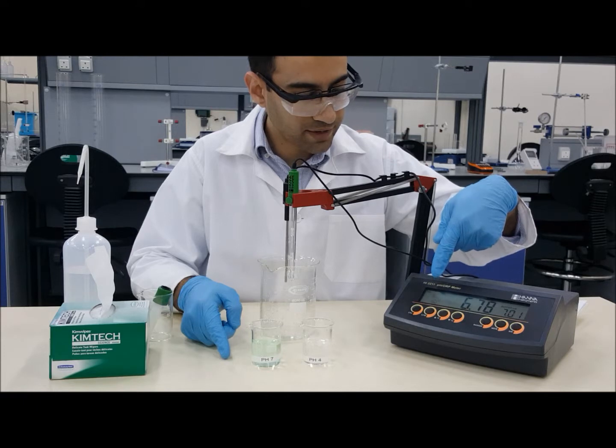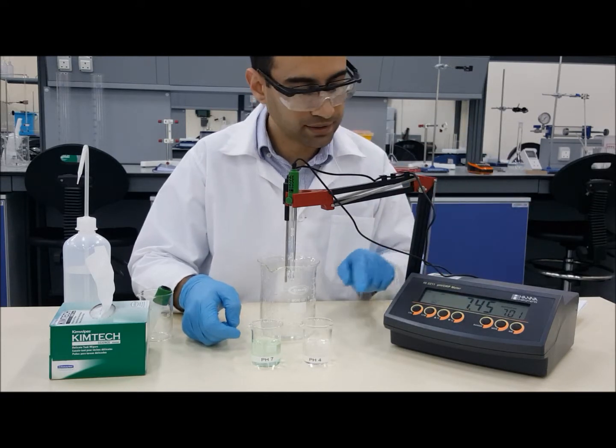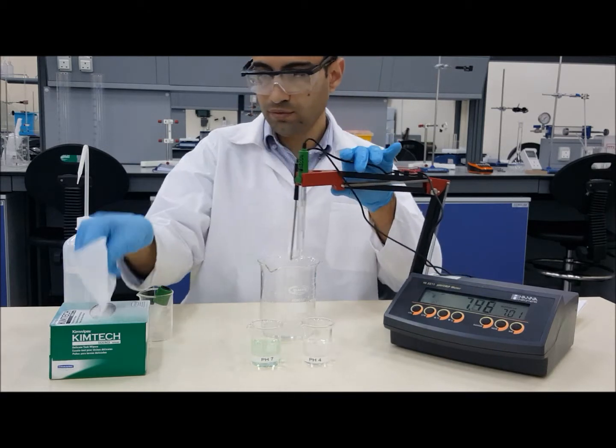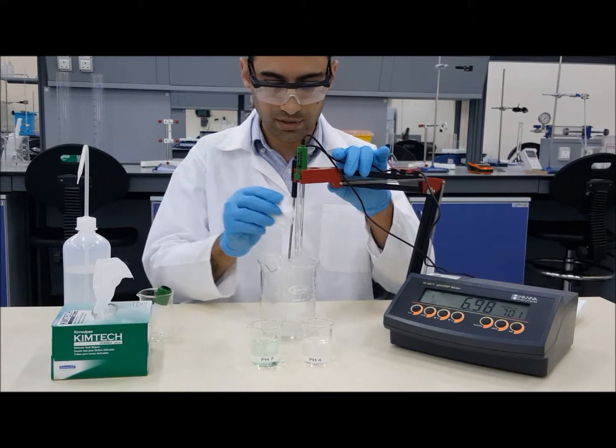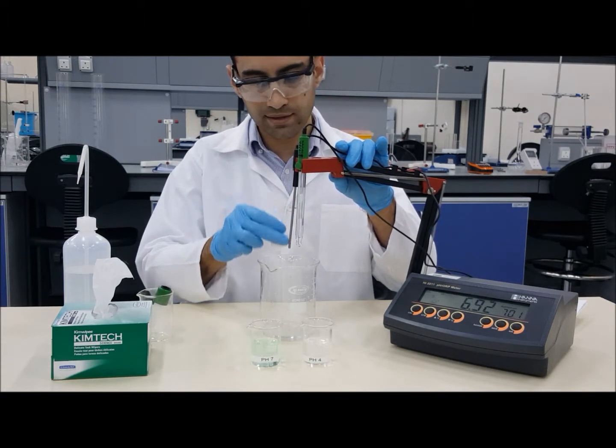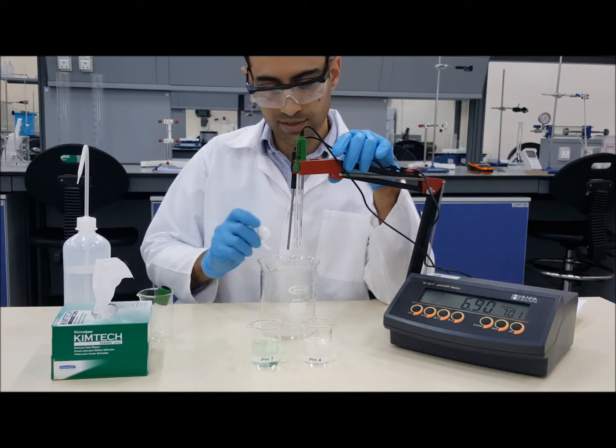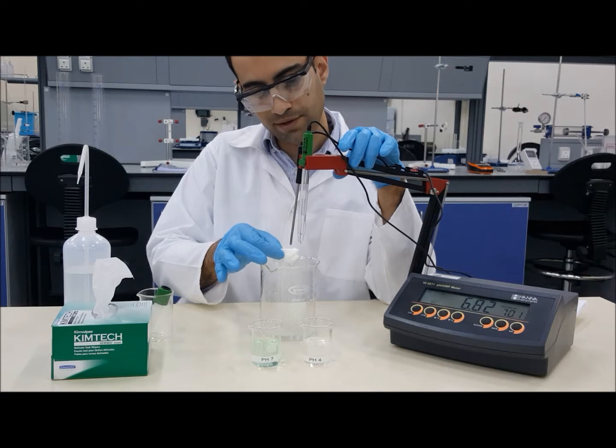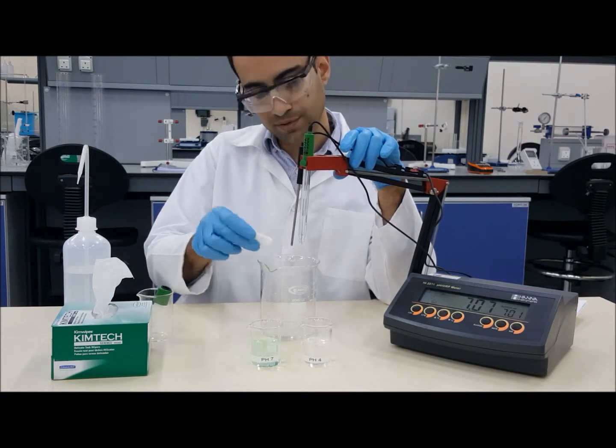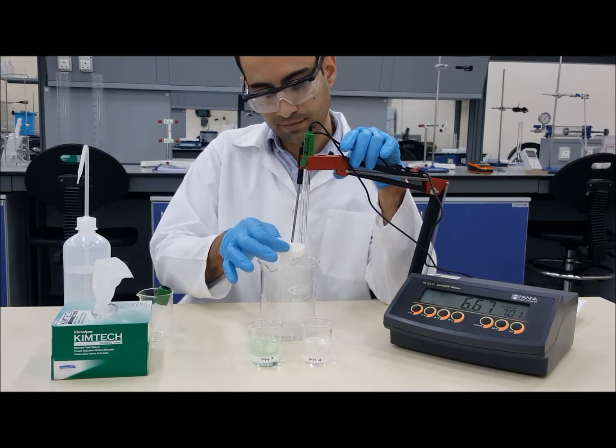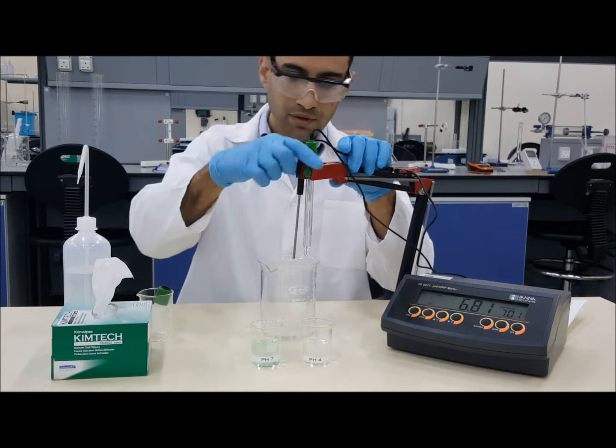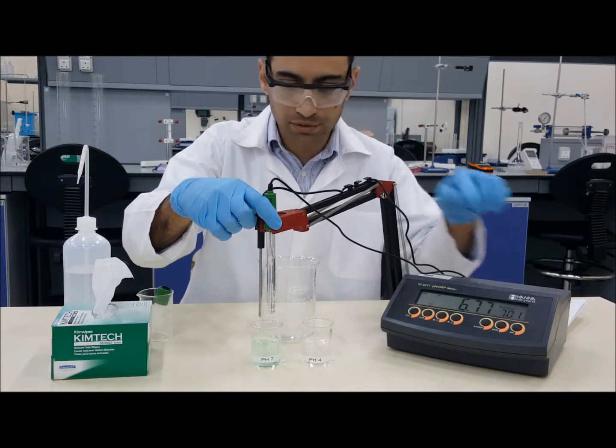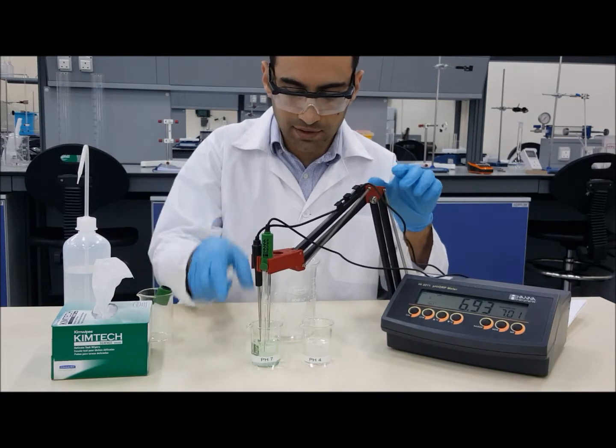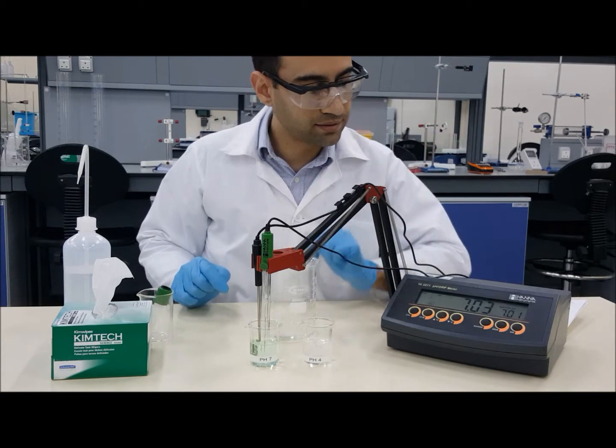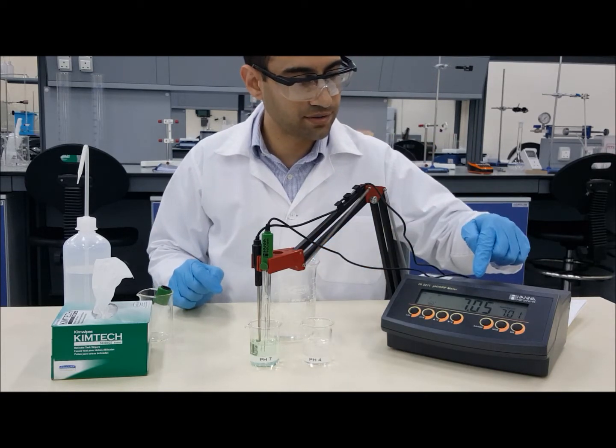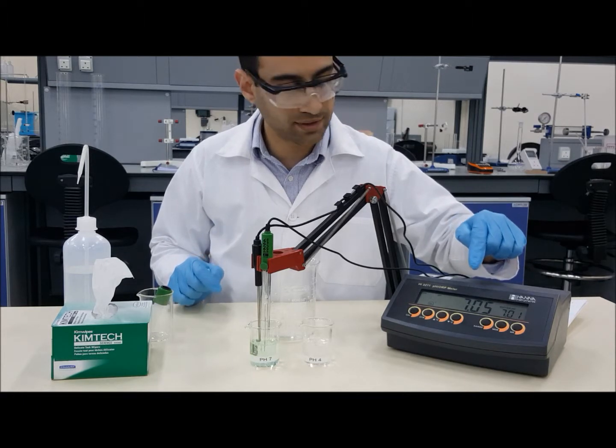We will get a flashing screen in here, which means it's waiting for the buffer solution. Before we get a reading, it's always good to use a tissue to make sure that the electrode for temperature is dry, and that little drop of chemical underneath the pH probe is just taken away. You don't need to dry it completely, something like that. Then we'll get it to buffer solution 7 as shown there, and give it some time to get to the right value. Now we can see the value is changing slowly. We'll need to give that some time to get stable.